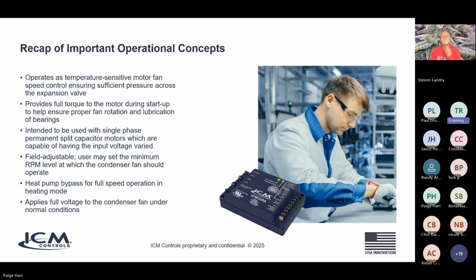It's field adjustable, so the user can set the minimum RPM level at which the condenser fan should operate. It has a heat pump bypass feature for full speed operation when you're in heating mode, and applies full voltage to the condenser fan motor under normal conditions for a heat pump, meaning AC conditions, whenever full voltage is needed. So for example, when it gets really hot outside and the pressure goes way up, you're not going to want to use variable speed control at all. So it just goes right into full speed above a certain range of temperature or pressure on the condenser coil or system.